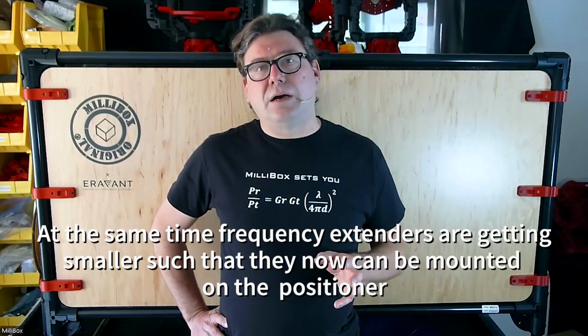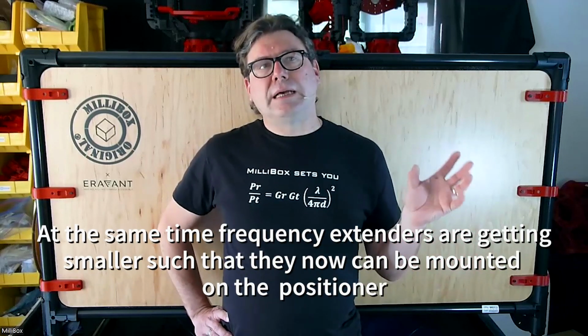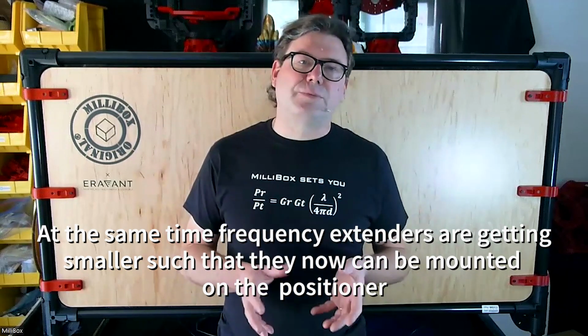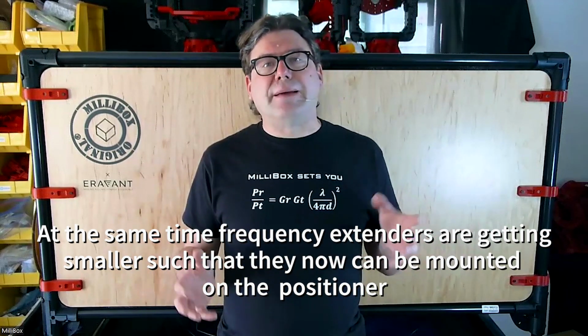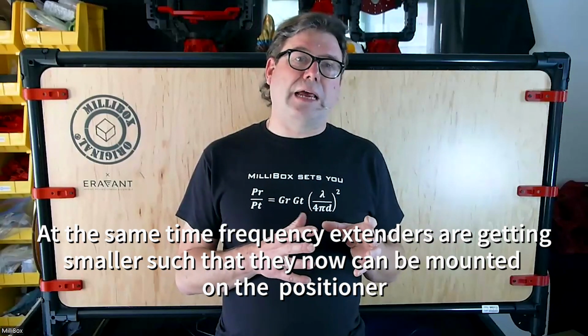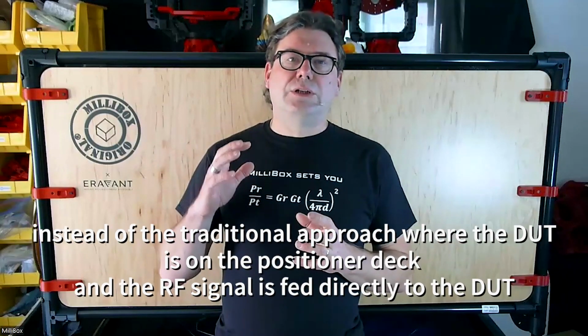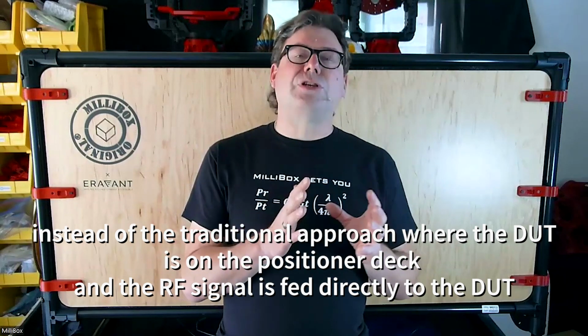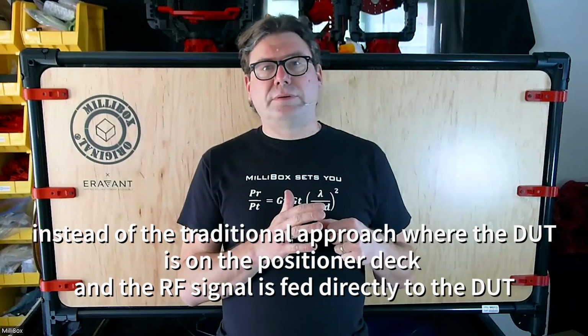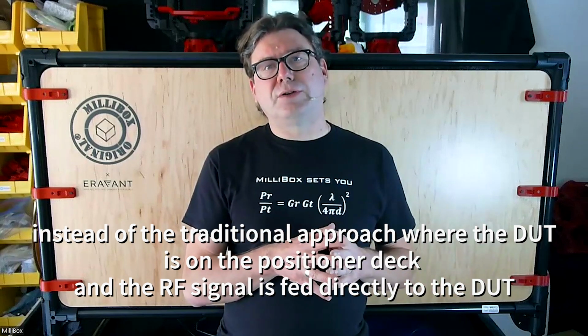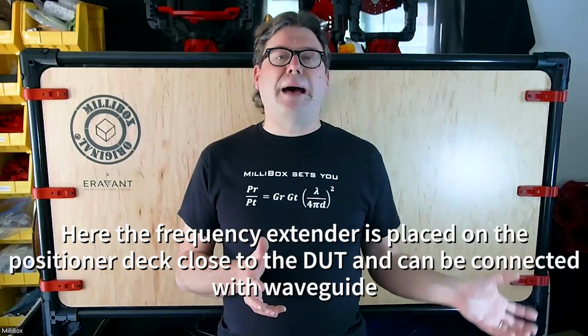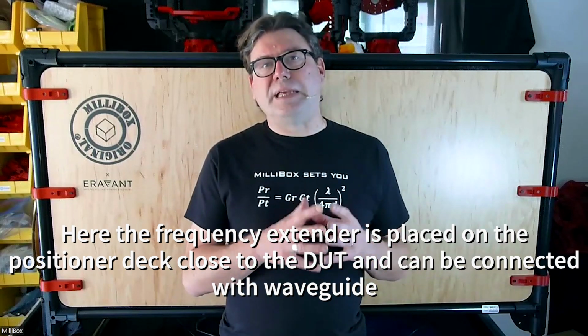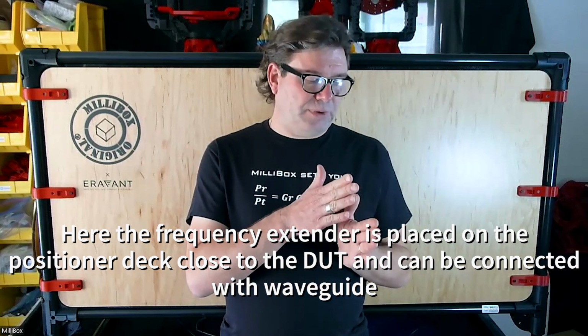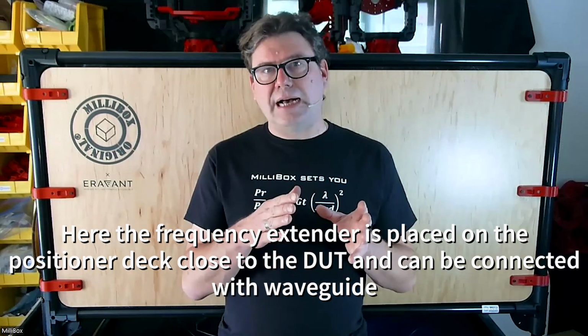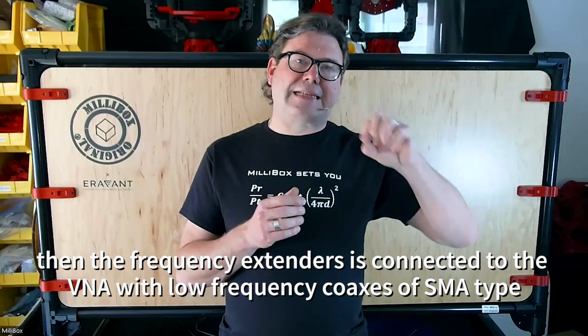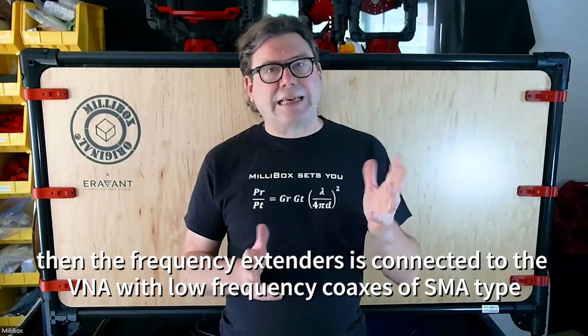So this makes it impractical, and the solution is, as the frequency extenders are getting smaller and smaller, we can now integrate them directly on the deck of our positioners, right? So instead of just having the DUT or the antenna array on the positioner and feeding the RF cable directly to this system, here we are going to mount the extender right on the deck behind the DUT, where we can make a connection between the extender and the DUT as a waveguide connection. And then from the extender to the VNA, we're going to go with SMA cable.